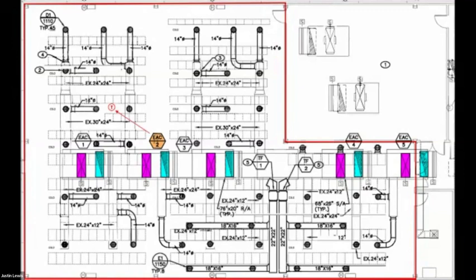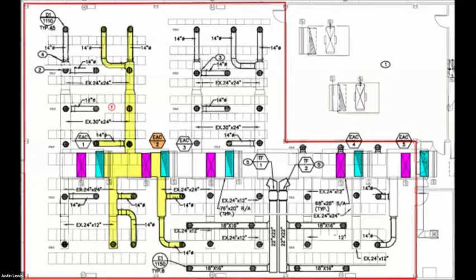So this means that if AC2's thermostat became satisfied, AC2 would ramp down to 80%, cooling would go off, and we would go into 100% recirculation mode. Now, this means that we were recirculating return air directly back into the shared supply plenum. So this resulted in hot air being supplied to cold aisles, because we had about 92 degrees return air. And that means we were discharging about 92 degrees back into the supply plenum. So the main taps that were off that main supply that were closest to that system were getting really warm air distributed.